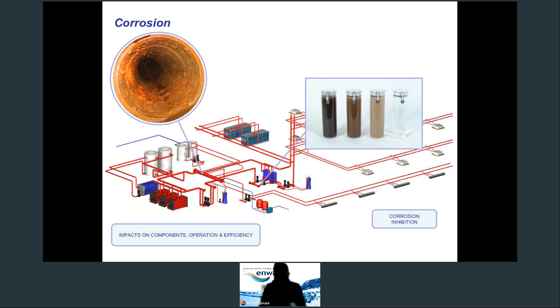Just a millimeter layer of scale reduces heat transfer efficiency by as much as 10%. So there needs to be consideration of the initial fill water and the makeup water, whether that be demineralized or softened water, depending on the type of systems that you're dealing with and the equipment that is being installed. Some manufacturers will require compliance with VDI 2035, whilst others don't. The direct impact of scaling is obviously scaling on hot surfaces, and it also impacts components such as pump seals and O-rings, which are some of the first components to experience problems.